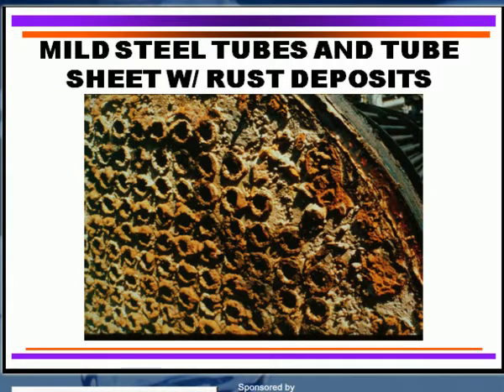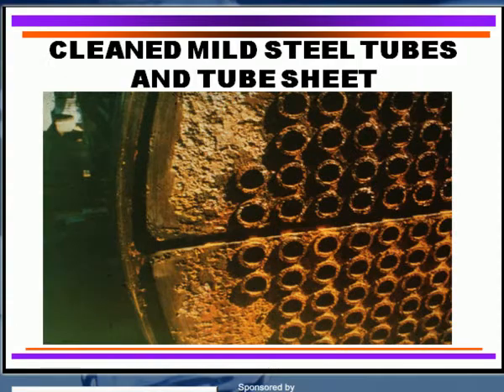Here's a good example of somebody that didn't do that. We have a lot of corrosion product buildup on the tube sheet as well as the tubes — in this case, carbon steel. If you clean that off, you can see that underneath there's been a lot of pitting attack that's occurred in the tubes as well as the tube sheet.